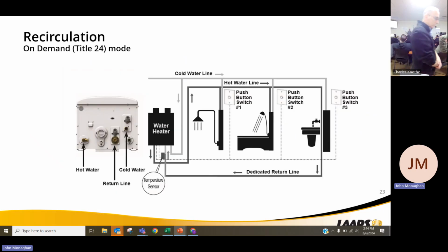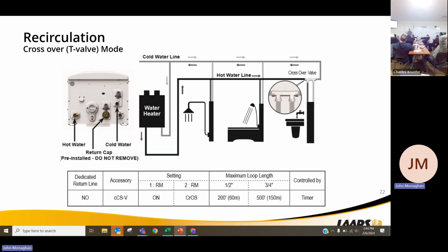Does it go on automatically if it's cold? If there's a cold front, does it just wait 20 minutes? Wait 20 minutes. And then what happens if you run out of water? You shouldn't run out of water. You shouldn't. Then you've overdrawn it, because once the tankless turns on, that recirc pump's no longer needed. Now it's pushing back the other way. Once the unit turns on, once I have water running through it and I'm delivering, that pump can drop out.